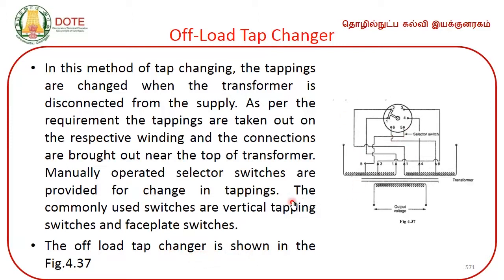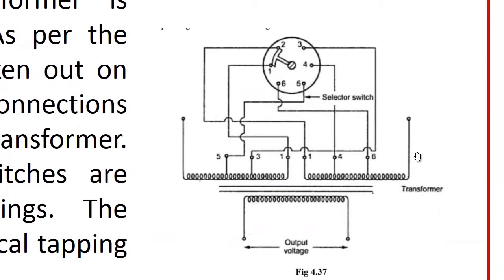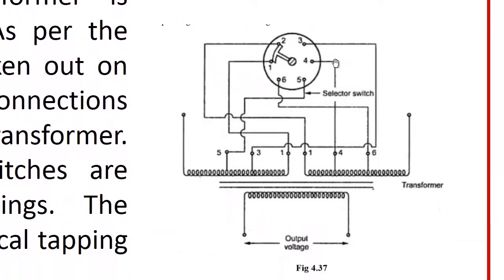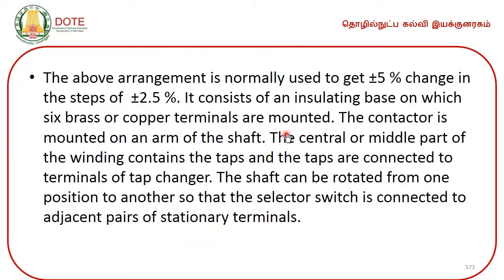Let me zoom this on. You can see here these are the selector switches through which the tappings can be selected: 1, 3, 5, then 1, 4, 6 and so on. The above arrangement is normally used to get a plus or minus 5% change in steps of plus or minus 2.5%.